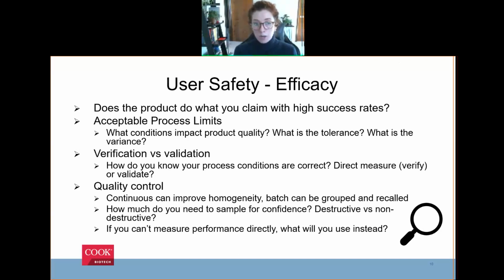But sometimes you have a process where you can't measure it directly for whatever reason. Again, I'm talking about sterility a lot, but it's very important in the medical industry. Sterility is an example of something that cannot be verified because the process of doing the measurement for sterility is destructive to the product. You have to open it and expose it to a non-sterile environment in order to do that test. So in order to be sure that the process conditions are such that my sterility is maintained, I do what's called a validation.